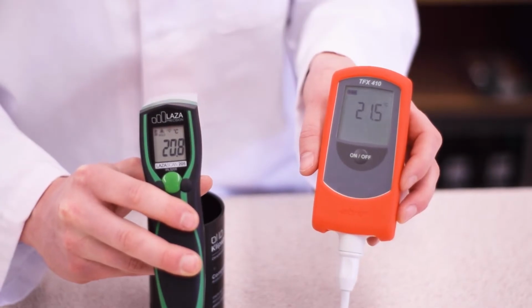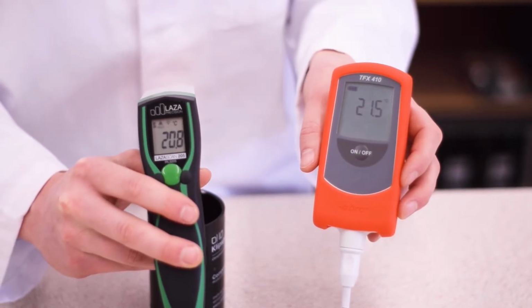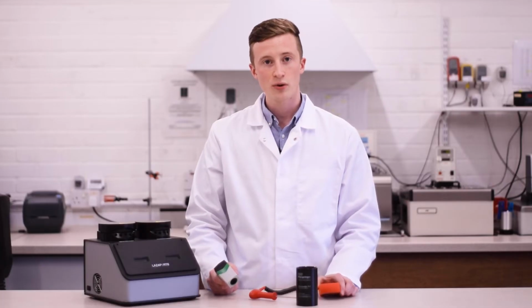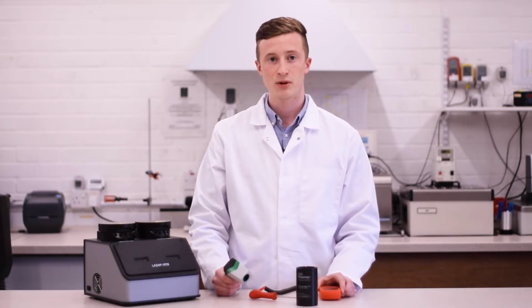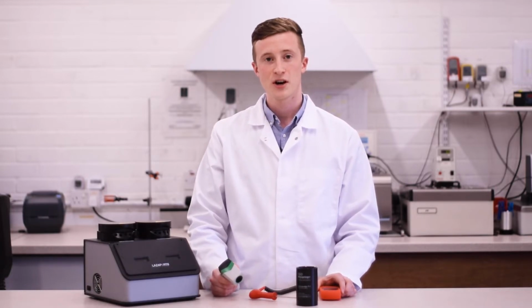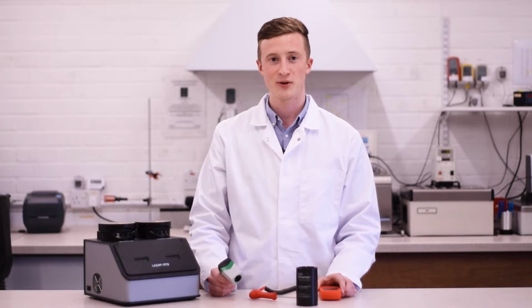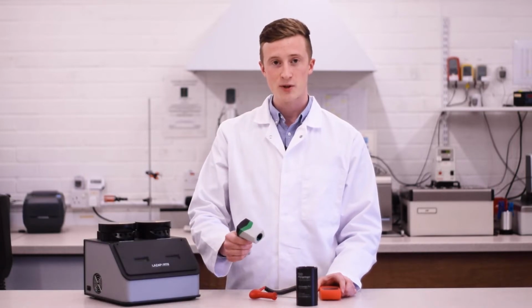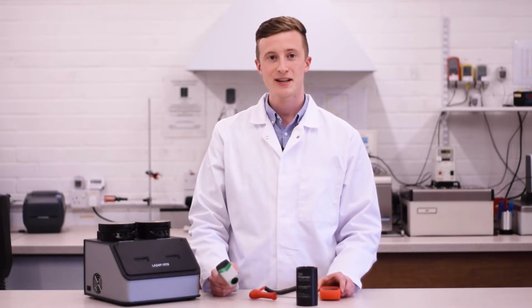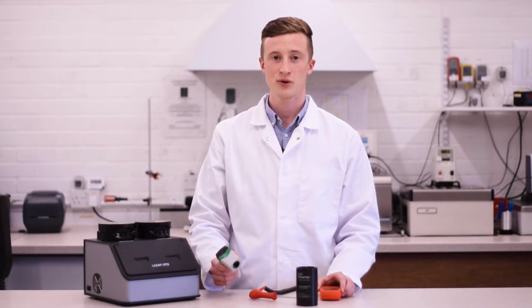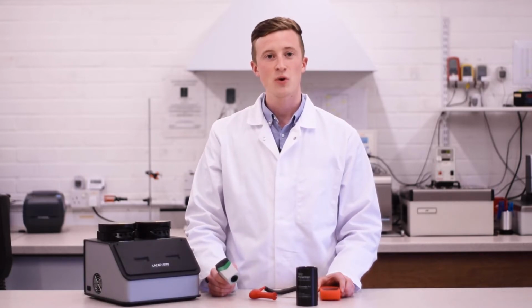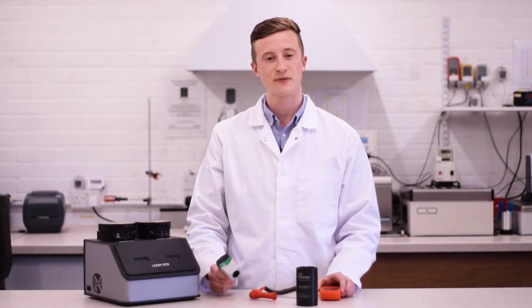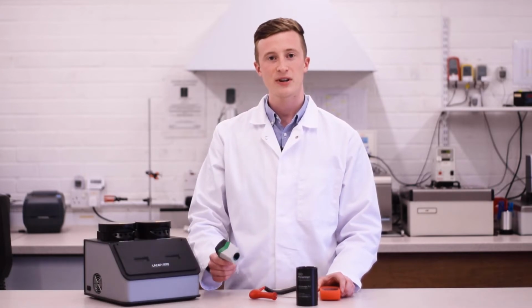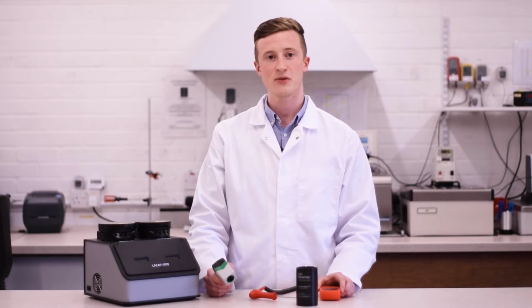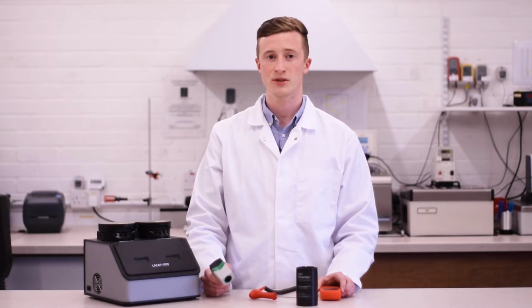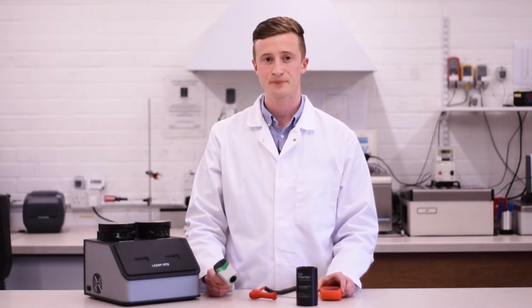Compare the reading from your infrared thermometer with the reading of your reference probe. Record the readings of your thermometer and reference thermometer on your calibration log. A free template can be downloaded below this video. The difference between the two, if any, indicates the accuracy drift of your infrared thermometer. What's excellent about this method is it's very budget friendly and very simple to carry out, especially if you have only 1 or 2 infrared thermometers, meaning it doesn't take you too long.